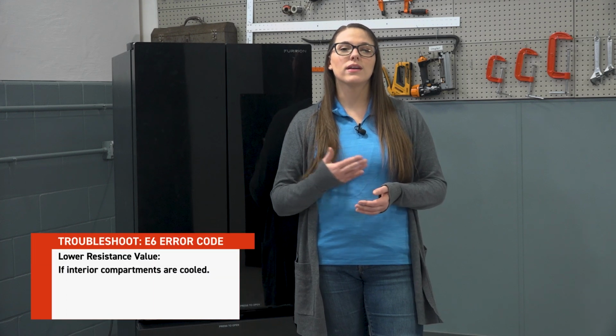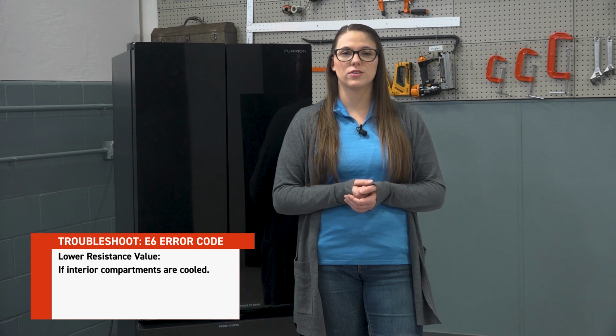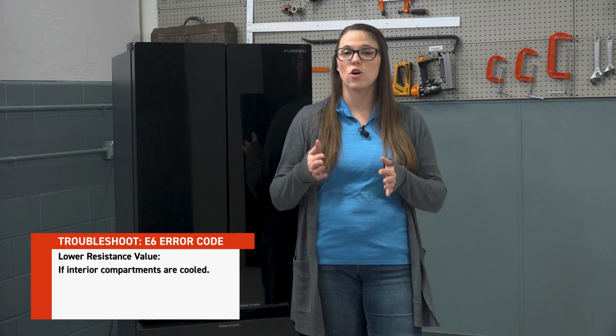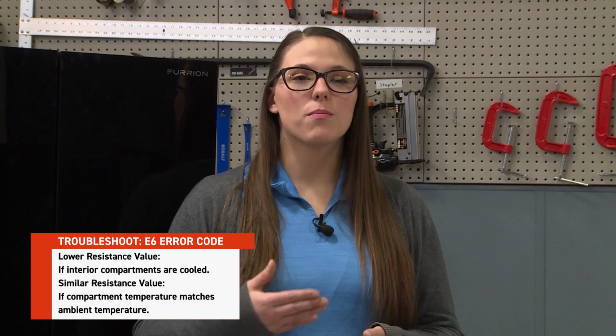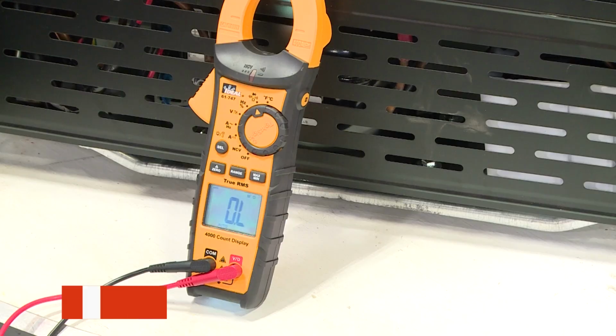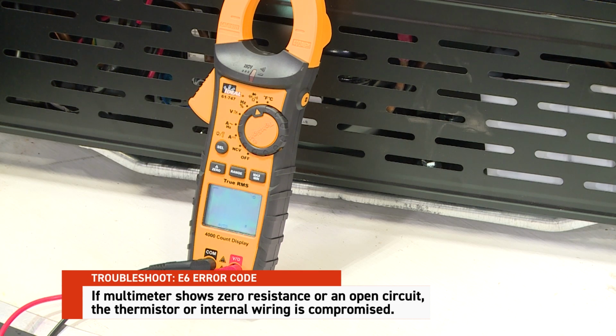However, the ambient temperature sensor should show a lower resistance value compared to the other sensors if the interior compartments are cooled. It should also have a similar resistance value to the other sensors if the compartment temperature matches the ambient temperature. If the multimeter shows zero resistance or an open circuit, the thermistor or internal wiring is compromised.